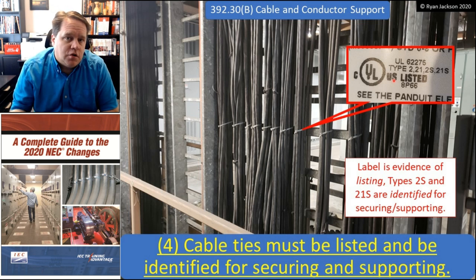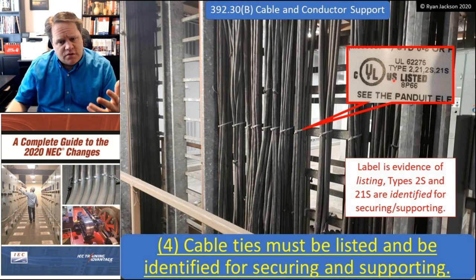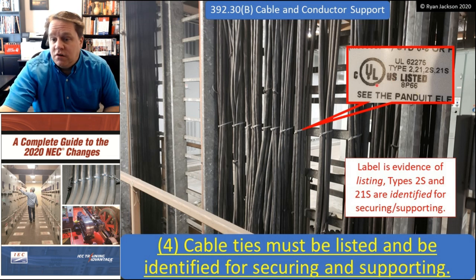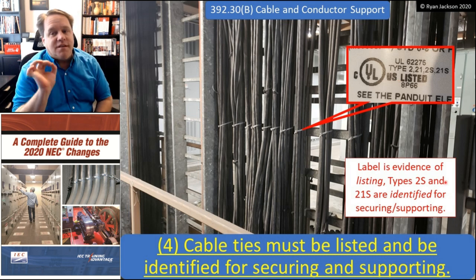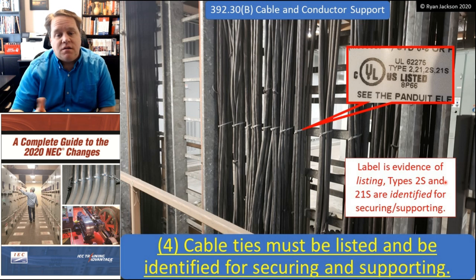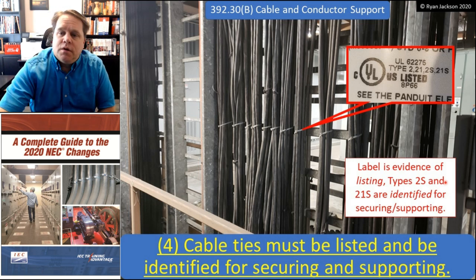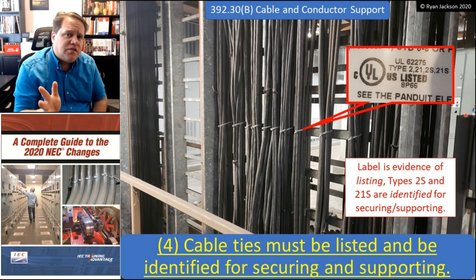The change here is for the cable ties — cable ties now have to be listed and identified for securing and supporting. This is actually a little more complex than it sounds. The cable tie has to be a listed product — we know what that means. Here on the package of my cable ties it says it's listed to Canadian standards and U.S. standards. However, that does not mean it complies with the rest of the sentence, because it also has to be identified for securing and supporting.